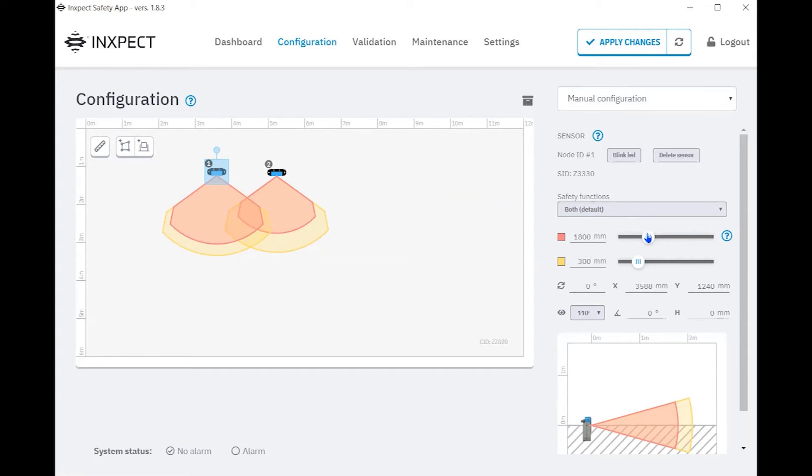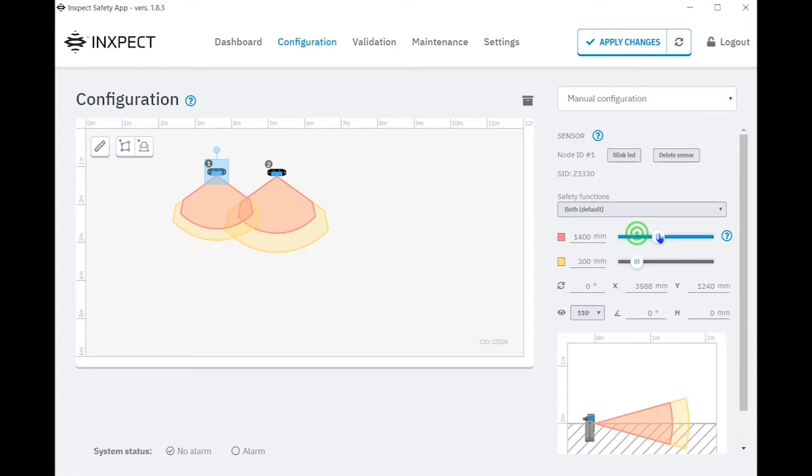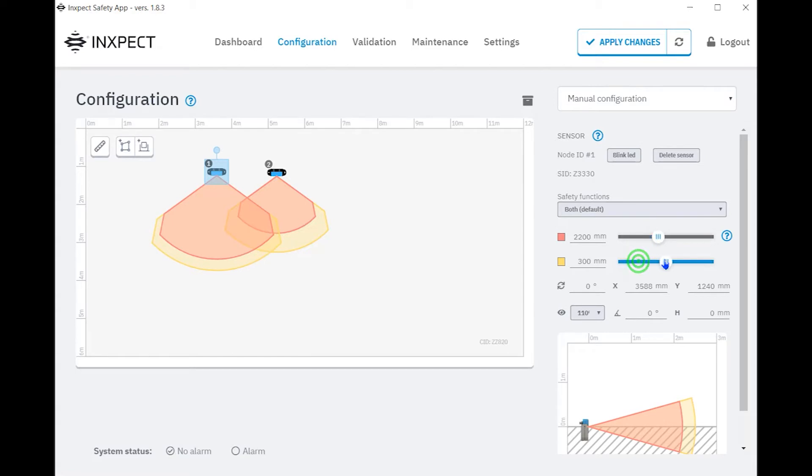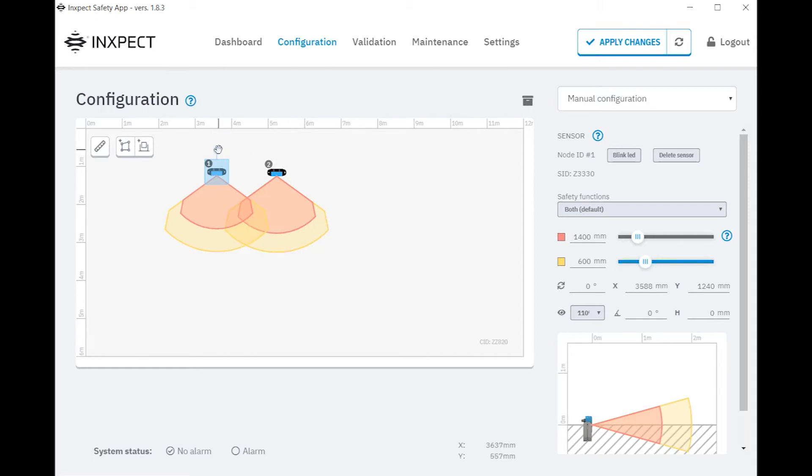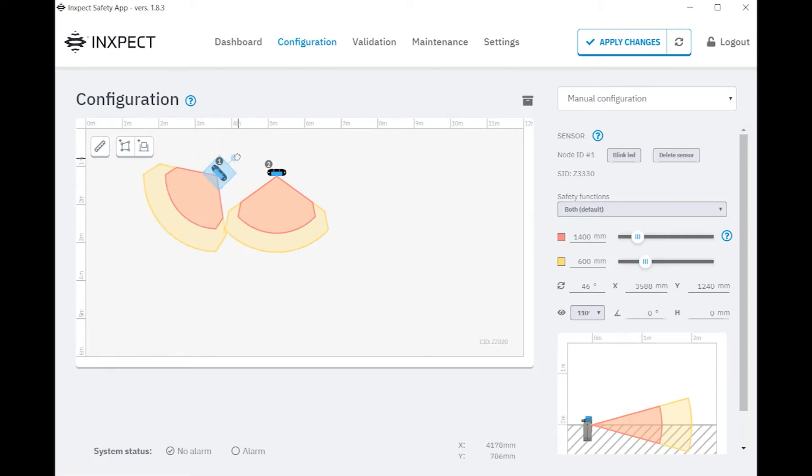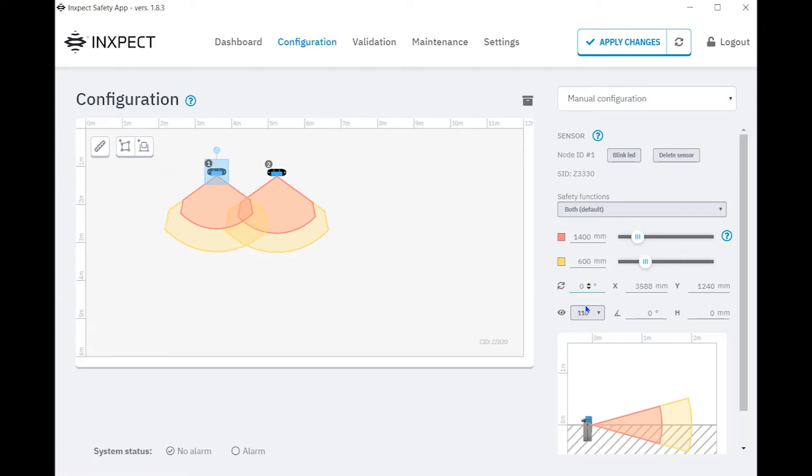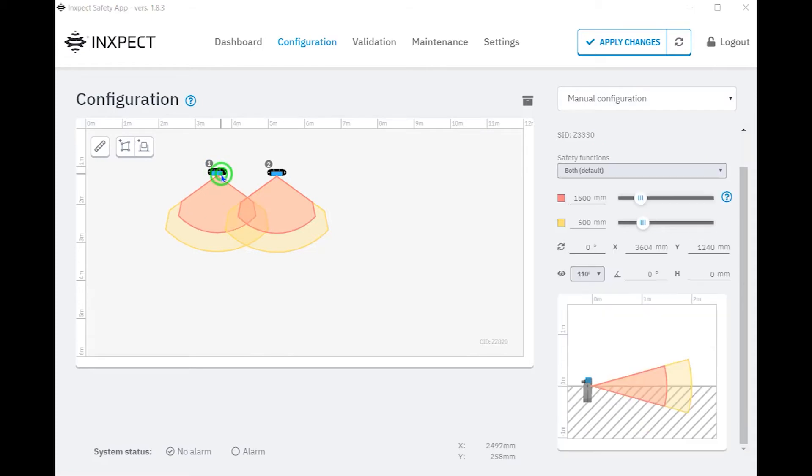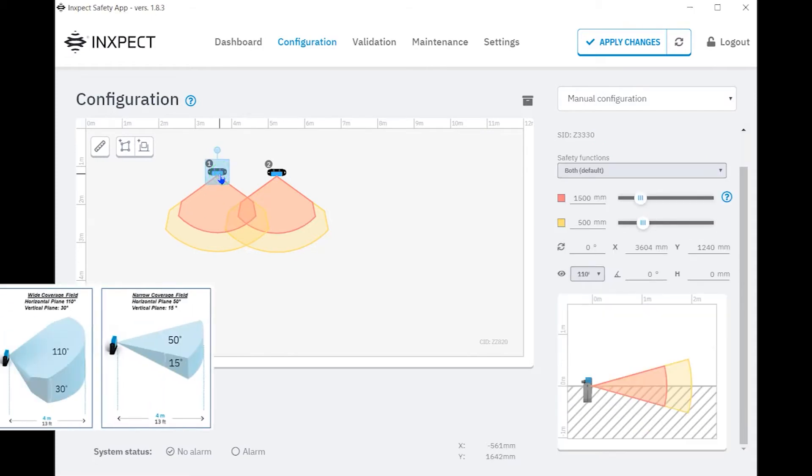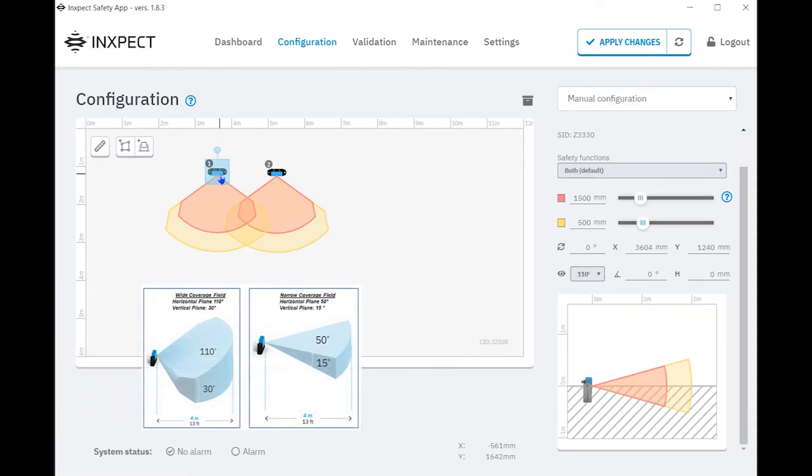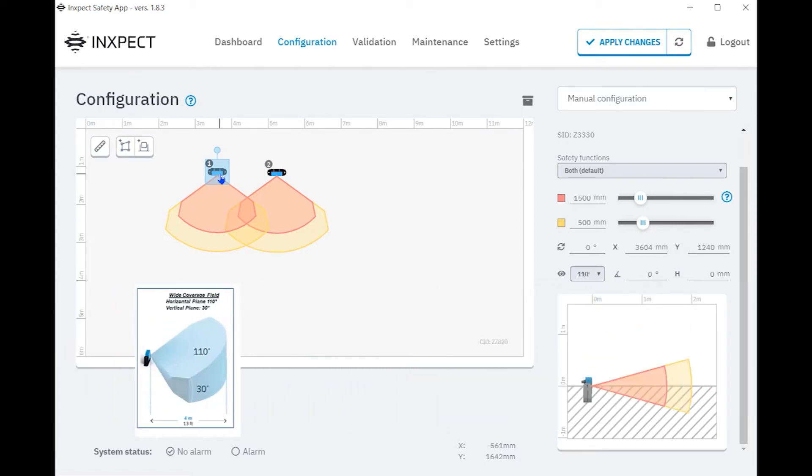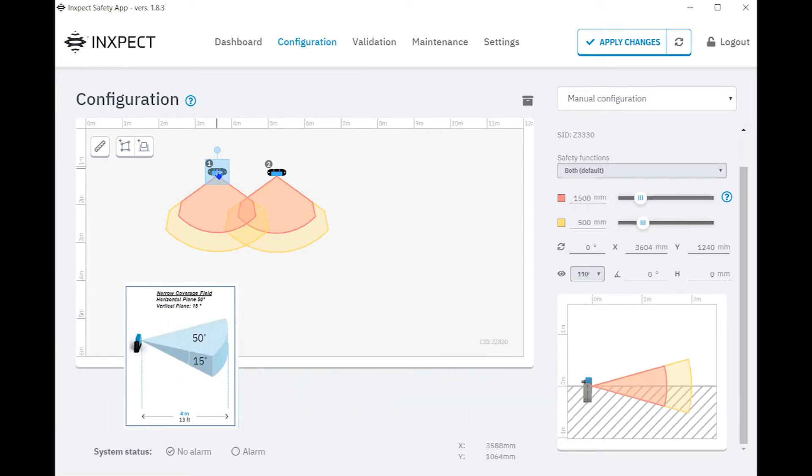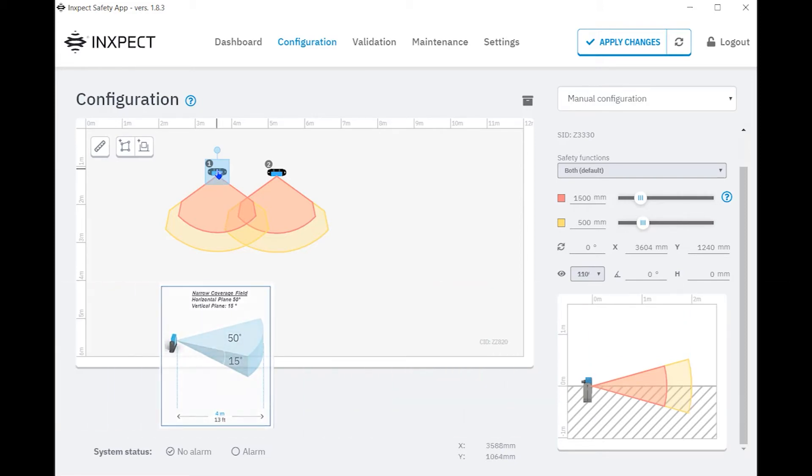On the right-hand side, we can adjust the length of the protective field and warning field. Rotation can be controlled manually by selecting the desired sensor and rotating to the desired angle. Manually entering the rotation angle can be done here. We previously discussed that the field of view can be configured for 110-30 or 50-15. By default, it is configured for 110-30. To change a field of view to 50-15, simply change the selection from 110 to 50 here.